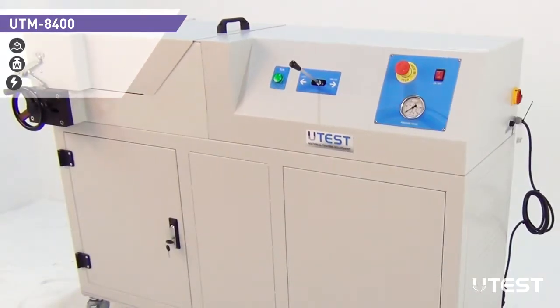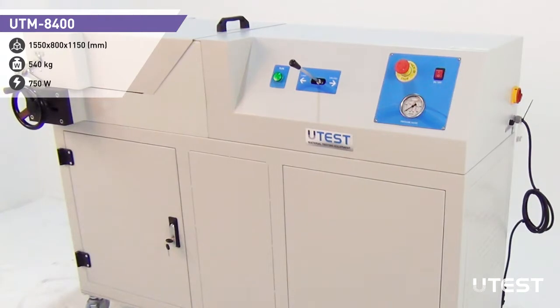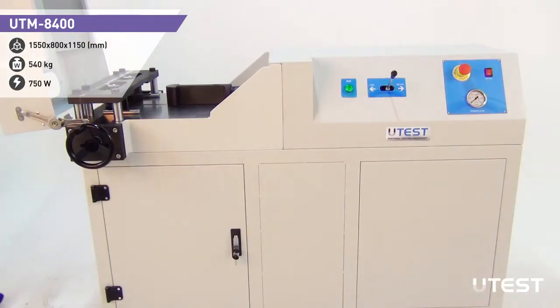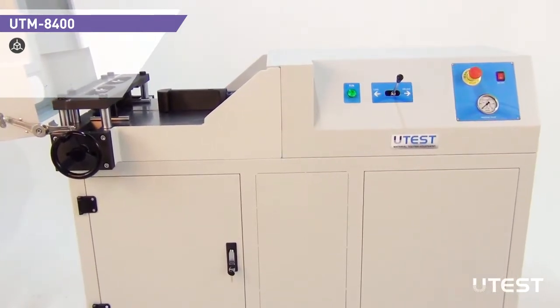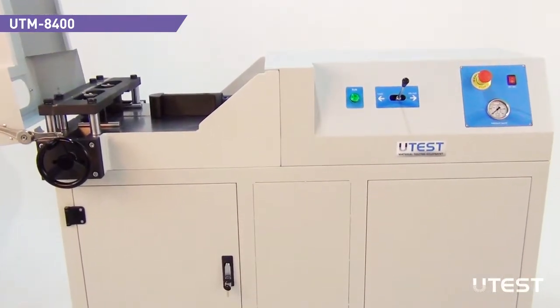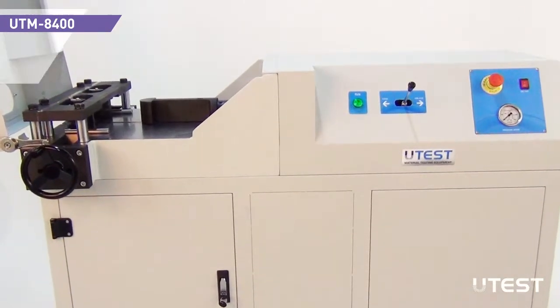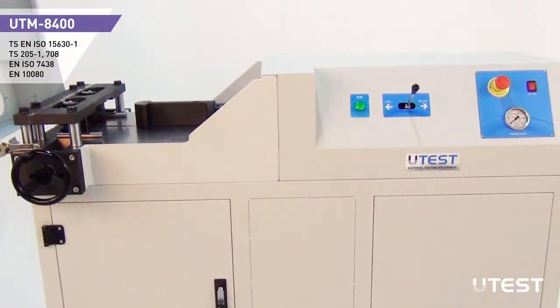The device can follow two methods of bending. The first one is bending the reinforced steel bar up to 90 degrees and then re-straightening back up to minimum at 20 degrees. The second method is bending up to 180 degrees.